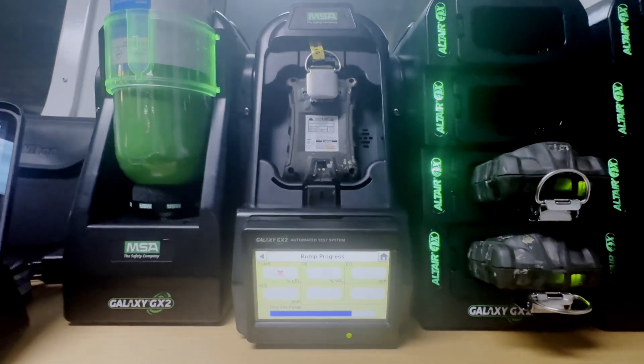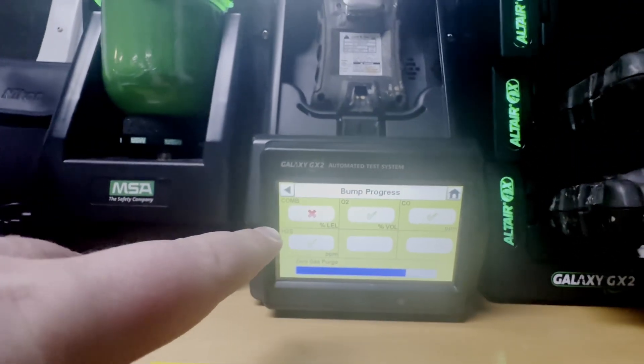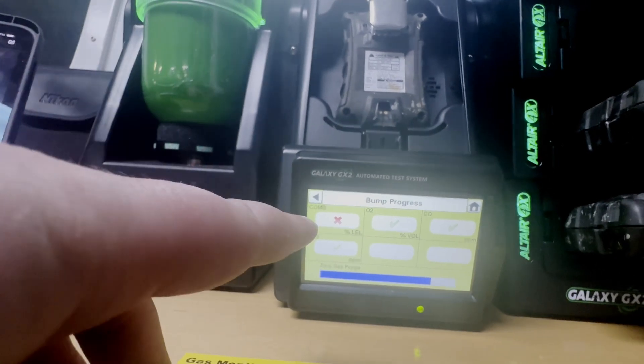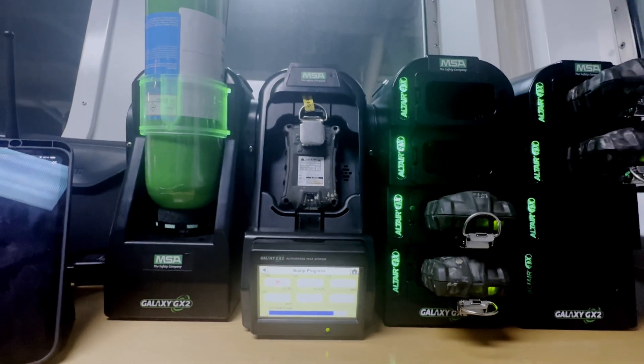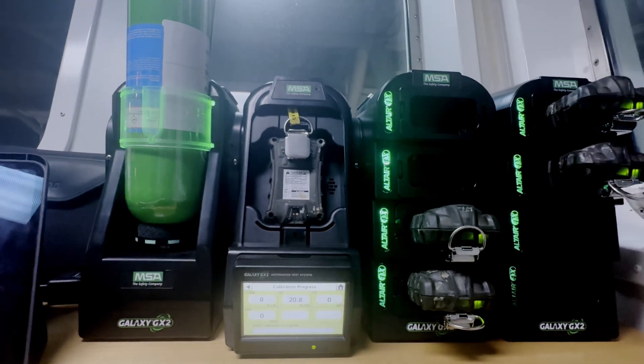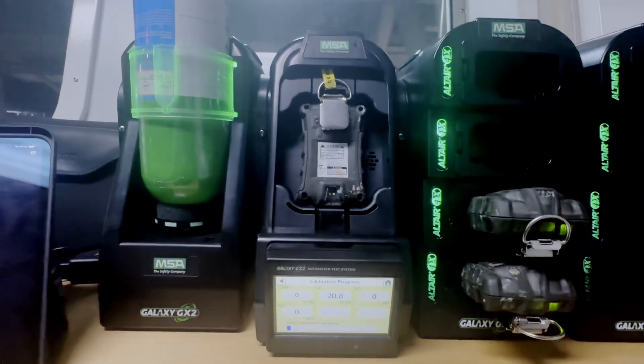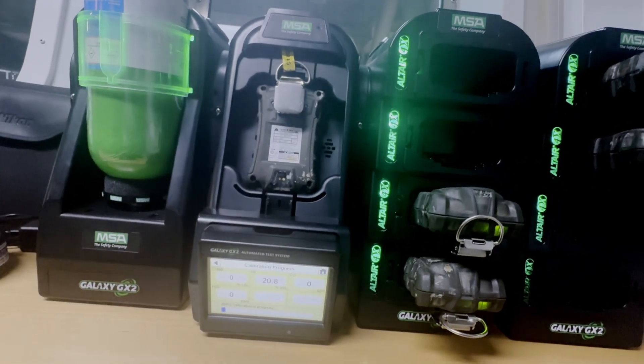While conducting another test for a gas detector, I noticed that one of the gases did not pass the test initially. This just means it's not calibrated properly. After the calibration device completes calibration, you will see a green tick appear and it will be successfully calibrated. Let's wait a little bit more and I'll prove that this is true.